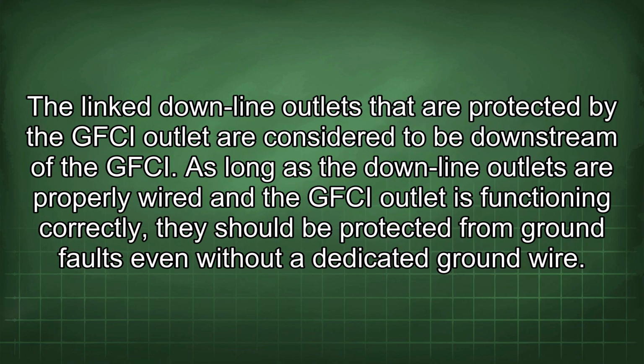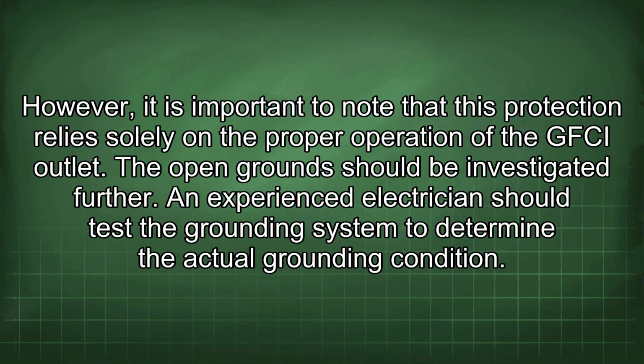The linked downline outlets that are protected by the GFCI outlet are considered to be downstream of the GFCI. As long as the downline outlets are properly wired and the GFCI outlet is functioning correctly, they should be protected from ground faults even without a dedicated ground wire. However, it is important to note that this protection relies solely on the proper operation of the GFCI outlet. The open ground should be investigated further.